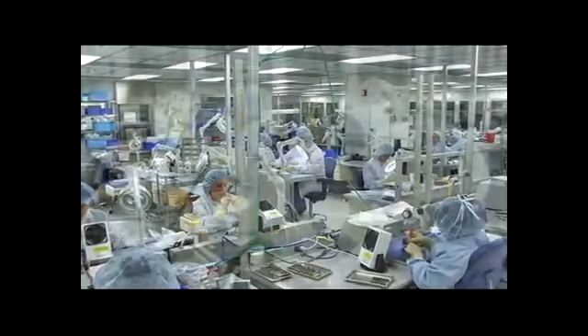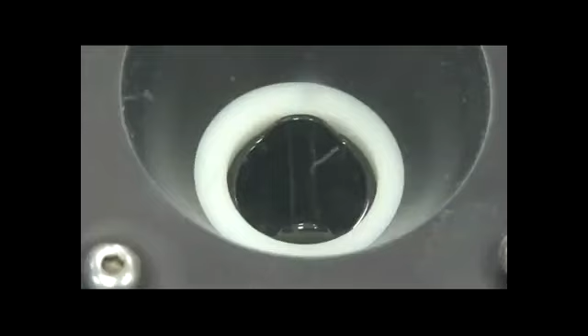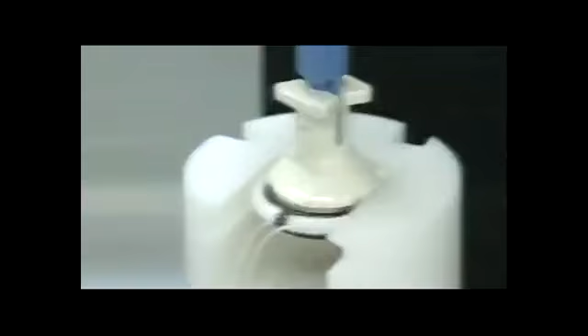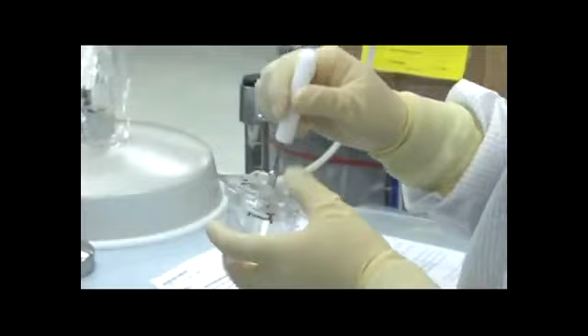The final stage of operation is the valve assembly process and inspection processes to ensure quality. The leaflets are inserted into the orifice. Proof-tested and leak-tested, the valve leaflet operation is tested individually before going to sterilization. Then, the orifice cup is prepared and attached to the carbon ring assembly. This process has numerous steps which include cup preparation, machine stitching, valve to cup assembly, hand sewing the cup and flange, and torque testing. Finally, the mechanical heart valve assembly undergoes one last quality inspection before it is packaged, steam sterilized, and shipped.